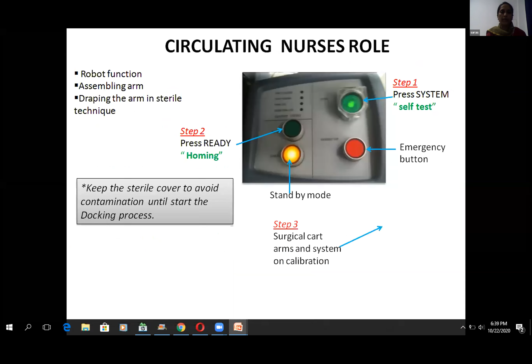So here, the robotic function must be checked before starting the procedures: assembling the arm, and draping the arm with sterile drapes. And this is the system for the calibration. A while ago, you saw in the picture there is a right port and a left port. This is to press the button to start the robot system and do the self-test. The second step is to press this ready button to home the system. After homing and the self-test, we stand by in this mode until the system docks in. This is an emergency button. If any consequences arise during the procedure, we use this button to take safety measures for the patient and the surgical team.